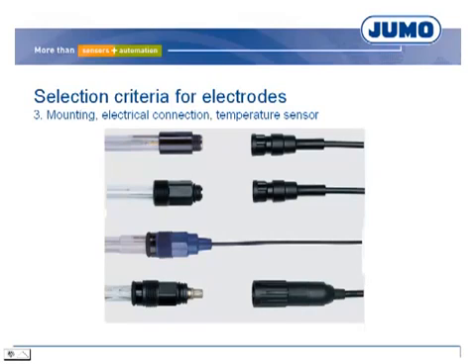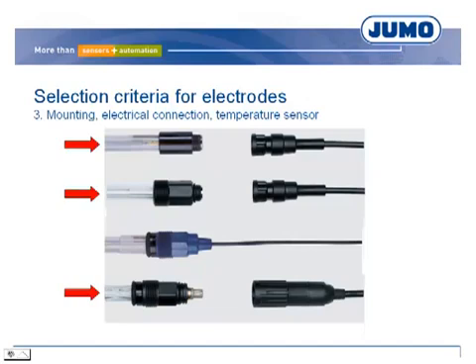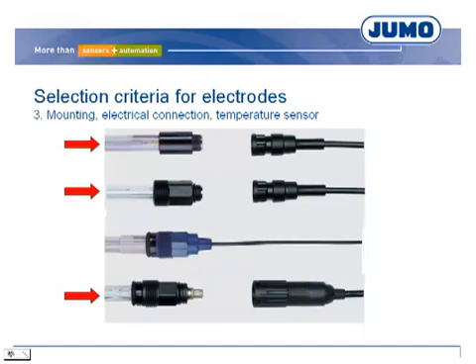Combination electrodes are available with plug cap or screw cap. The electrical connection can be realized either via a plug system or with a fixed cable. Electrodes with resistance thermometer are also available. It is very important that the plug contact is always dry — even a little humidity can cause incorrect measurement due to the high-resistance measuring circuit.